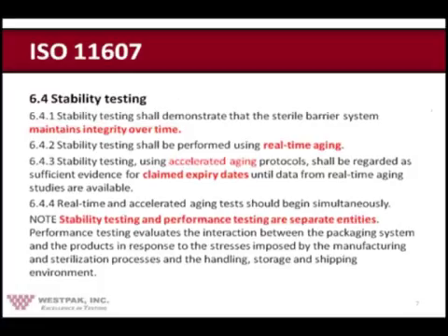And that's important because how in the world are you going to claim that something has an expiry date of 2 years without accelerated aging? That would require that you keep the darn thing on the shelf for 2 years and then start selling it after you verified it was good, in which case you'd need a longer expiry date. So it's required in order to catch up with what's in the future.